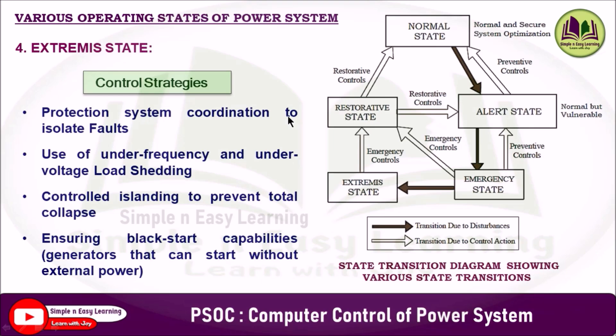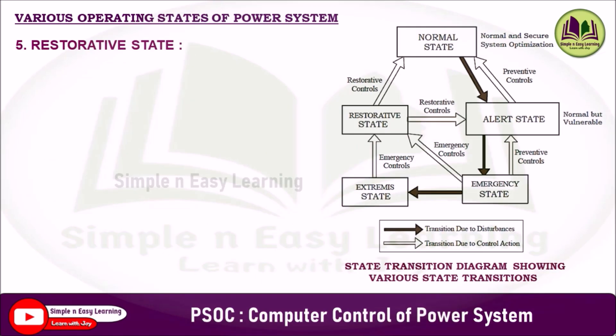Small self-starting generators — such as diesel generators or hydro units that do not need grid power to operate — are used to start generation, gradually energize nearby transmission lines and substations, and then use this power from the black start unit to bring larger thermal and gas power plants online.